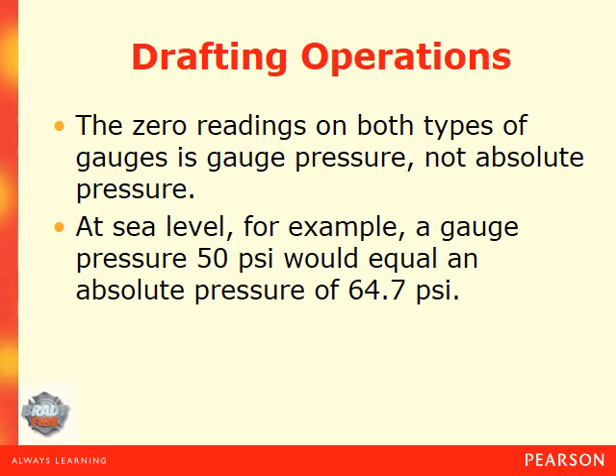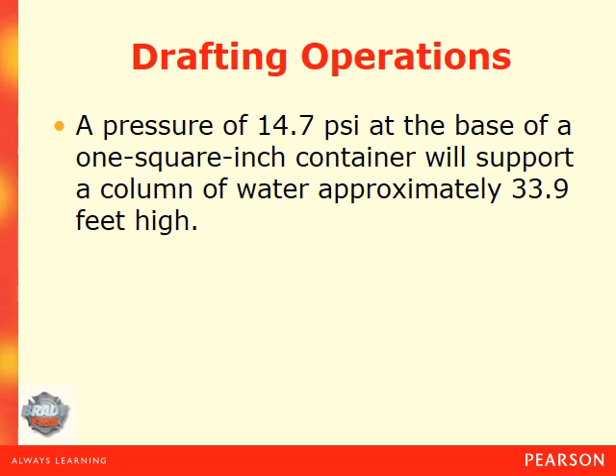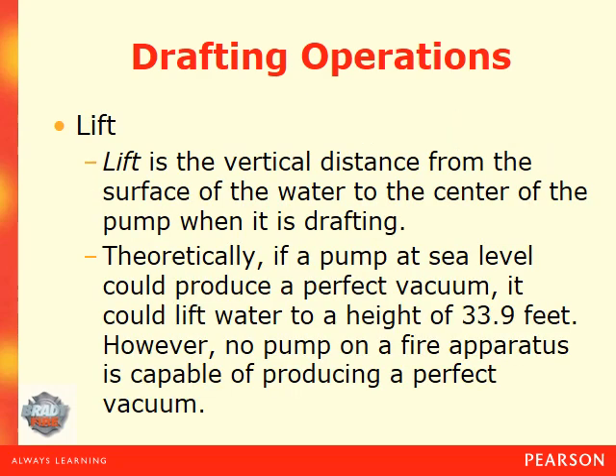At sea level, a gauge pressure of 50 psi equals an absolute pressure of 64.7 psi. Readings below zero on the compound gauge are measured in inches of mercury. One inch of mercury equals an absolute pressure of 0.49 psi, and atmospheric pressure of 14.7 psi equals 29.92 inches of mercury. A pressure of 14.7 psi at the base of a one-square-inch container will support a column of water approximately 33.9 feet high. Lift is the vertical distance from the surface of the water to the center of the pump when drafting. Theoretically, if a pump at sea level could produce a perfect vacuum, it could lift water to a height of 33.9 feet. However, no pump on a fire apparatus is capable of producing a perfect vacuum — if a pump is in excellent condition drafting at sea level, it should be capable of obtaining a lift of 25 feet.